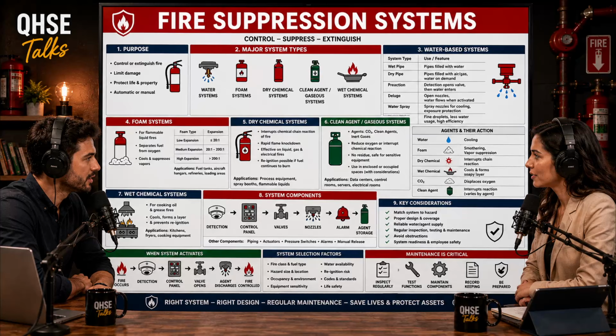But if they knock the head off in a preaction system, what happens? The pressurized supervisory air in the pipe escapes. The system triggers a trouble alarm at the panel, alerting maintenance that a pipe is breached. But the water valve in the riser room does not open, because the smoke detectors haven't sensed any smoke.